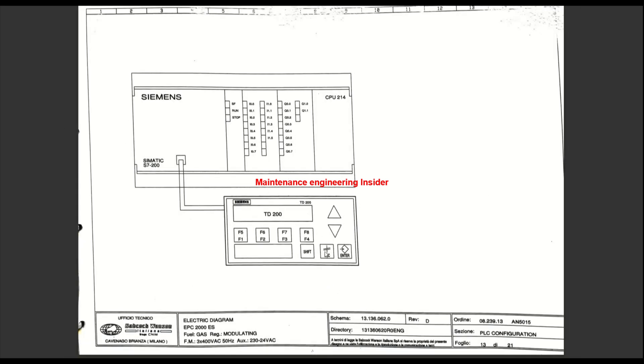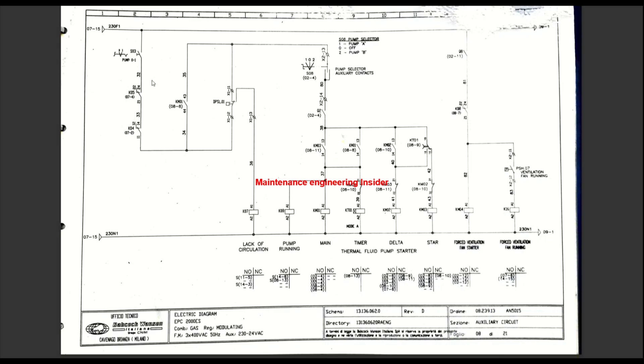This is a PLC. It also shows that this signal is coming from foglio H6, where you will troubleshoot to find the 'low fluid circulation' input. This input comes from contact K07 on page H6. On page 8, line 6, you can find K07 — the lack of circulation relay. This is page 8, line 6 — find K07 and troubleshoot from there.